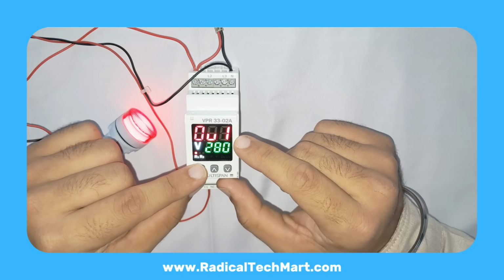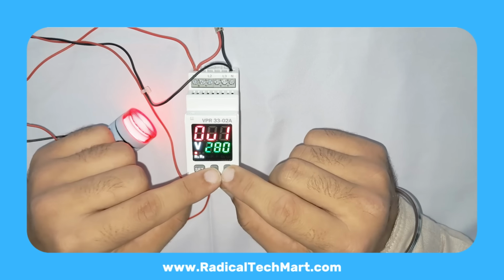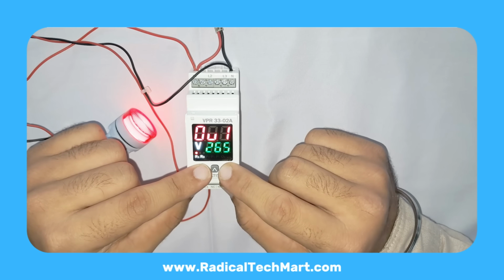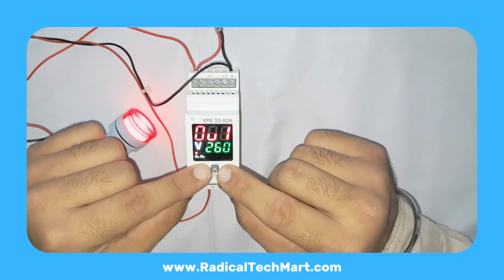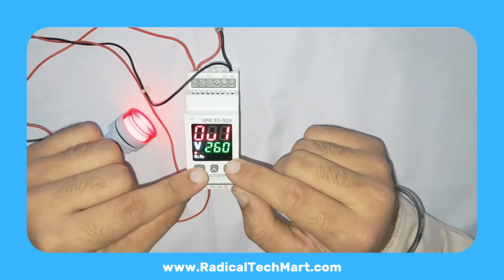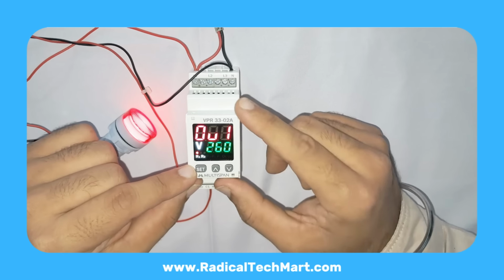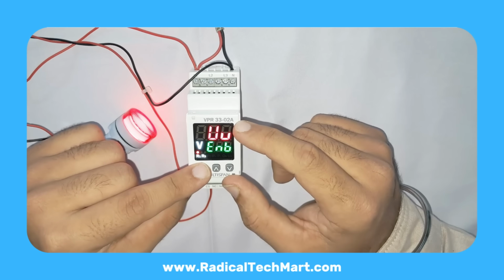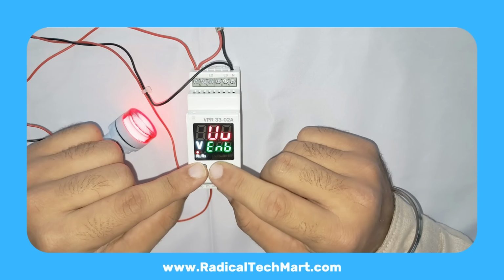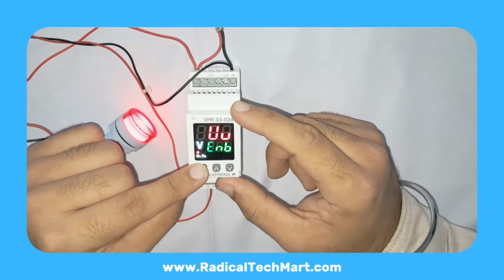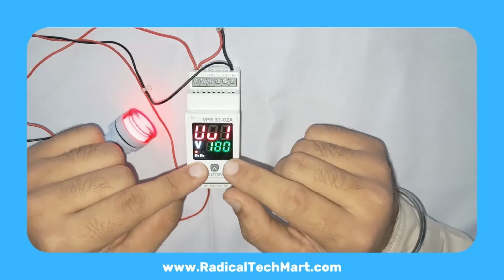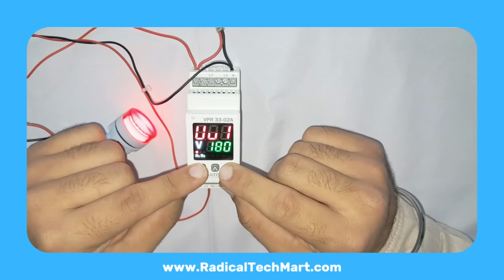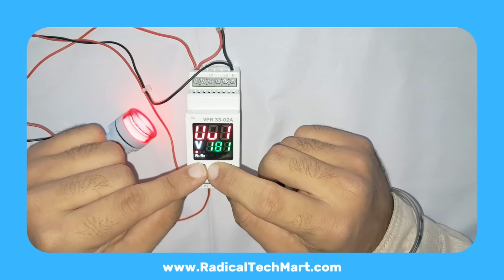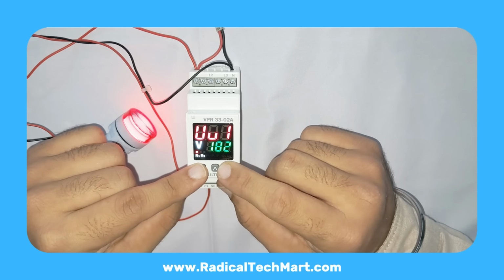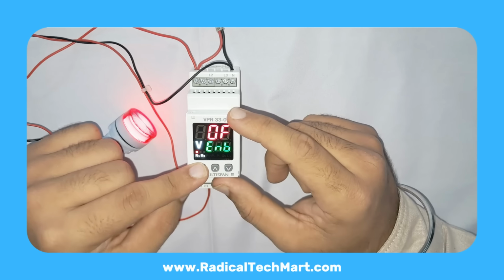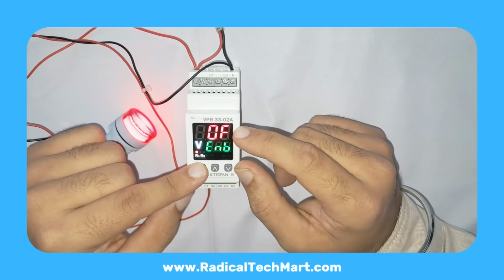Now you can set the overvoltage trip level. The default value is 280 volts for line to neutral single phase. If you want, you can change it to 260 volts, 250 volts, etc. using up-down. Press Set to confirm. Next comes UV, undervoltage. Again, you can enable or disable. Press Set. Now set the undervoltage level. The default value is around 180 volts. You can set a higher or lower level as per your application. Press Set to move ahead. The next parameter is OF, over frequency.